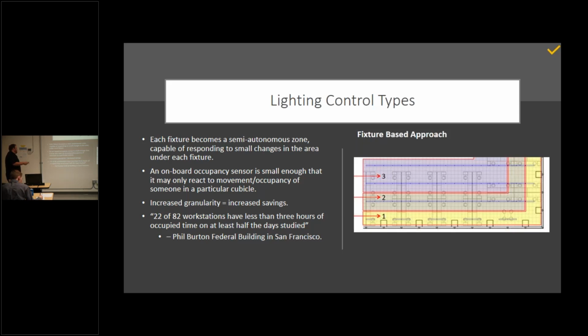So it has a higher chance of only reacting to the movement in its vicinity that it's actually applicable to. What that means is that if you have increased granularity, you get increased savings. A study done at the Phil Burton Federal Building in San Francisco found that office workers were only at their desks for less than 3 hours of their day. So if you can capture that savings of when a person's not at their desk, then that can add up over time, especially if it's a huge office building.